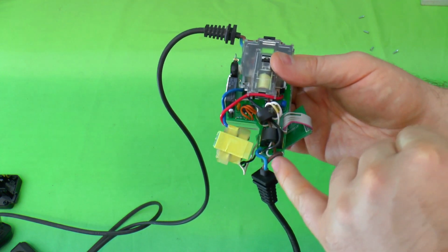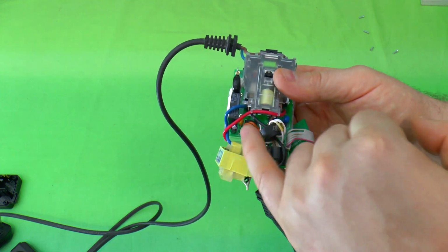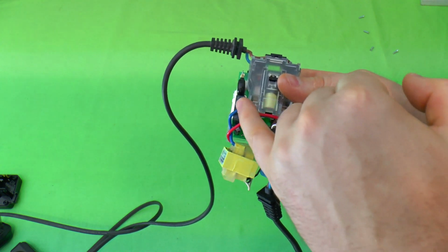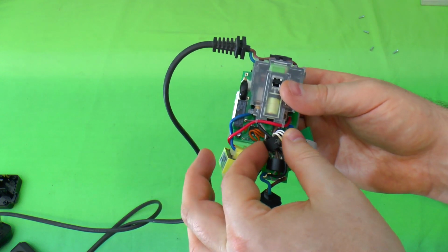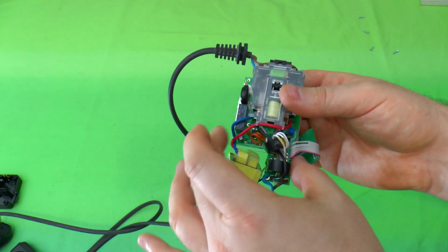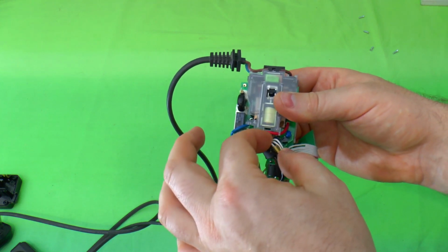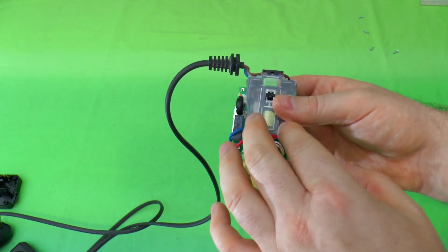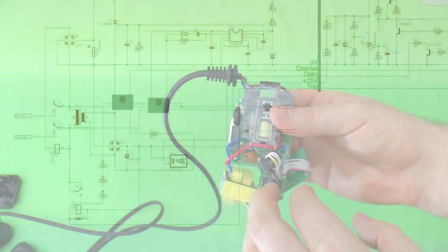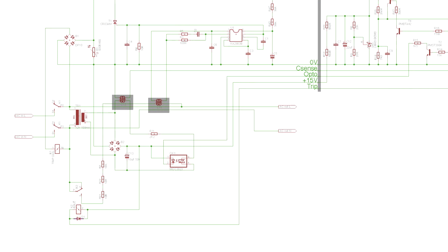You get this live wire coming through, you've got power flowing back through several times around through there and then back. So it's deliberately creating an imbalance there. And that's how the test circuits work on these things. You basically create a deliberate imbalance and make sure that the circuit actually detects it and trips. And on this, that's done with a relay.